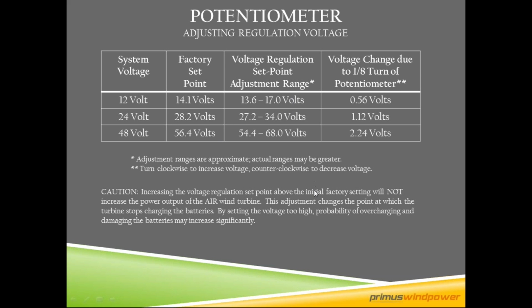Morningstar and I have worked closely with Trojan and AGM batteries, which are primarily what's used in the oil and gas industry. We've discovered that for oil and gas, it's better to set this a little higher, 14.3 or 14.4 for a 12-volt system, for example. So you can turn that pot screw up, and here are the adjustment ranges. All of this is in the manual, with exactly how to do it.